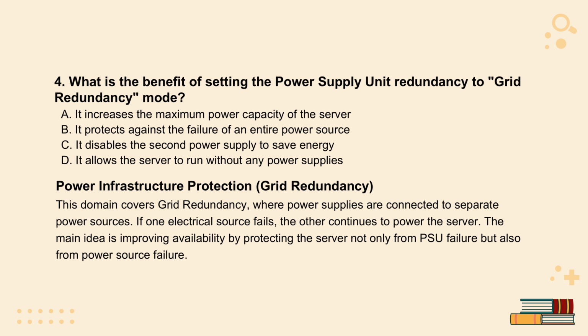Question 4 focuses on power redundancy. It asks: what is the specific benefit of setting the power supply unit redundancy to grid redundancy mode? The options usually involve things like saving power or adding capacity. This one trips a lot of people up. The correct answer listed is B, protects against the failure of an entire power source. But wait, don't all dual power supplies do that? If one breaks, the other takes over, right?